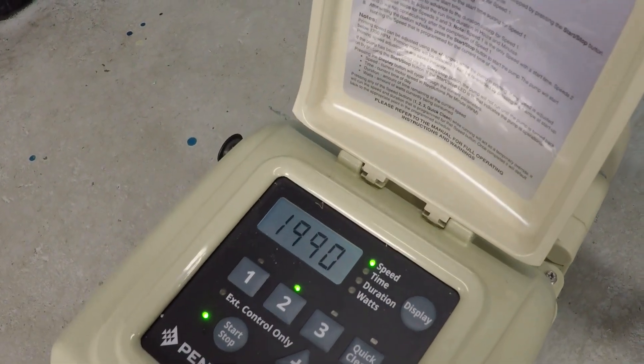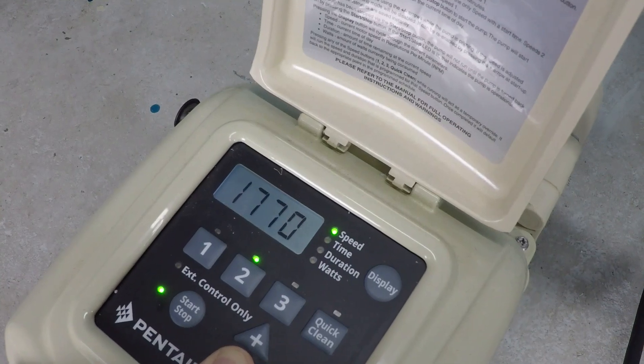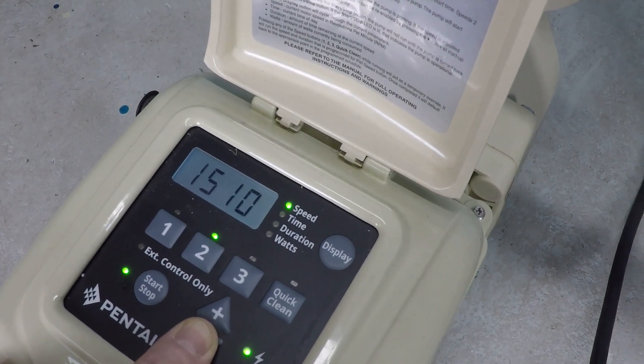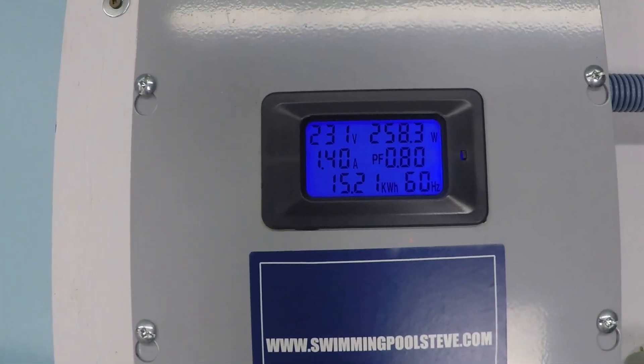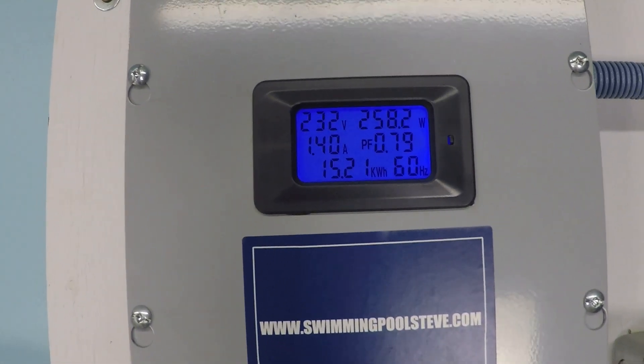Now let's drop down to 1,500 rpm. Just as expected, we're seeing 41 gallons per minute. Look at the power consumption though — way down to just 258 watts per hour. That's 41 gallons per minute at 1,500 rpm.